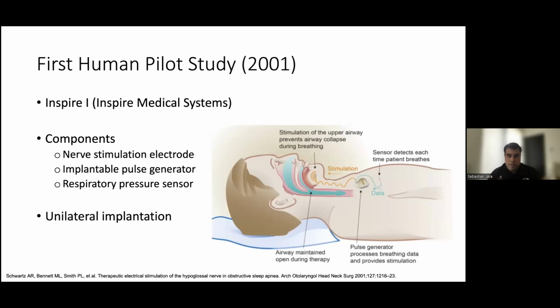And this was a device that had 3 different components. It had a nerve stimulation electrode, which went around the hypoglossal nerve, an implantable pulse generator, which generates the electrical impulse, and the respiratory pressure sensor. This is a piezoelectric pressure sensor that's placed against the pleura to detect respiratory effort. And so the way that this works is by detecting the end of expiration, a signal is generated from the respiratory pressure sensor, which goes to the implantable pulse generator, which in turn sends a pulse that activates the hypoglossal nerve at the onset of inspiration.